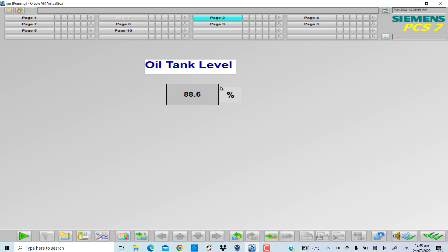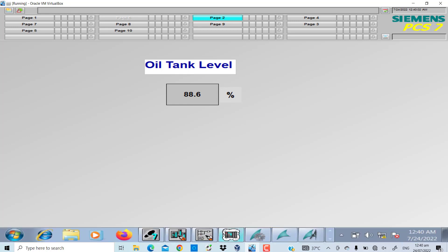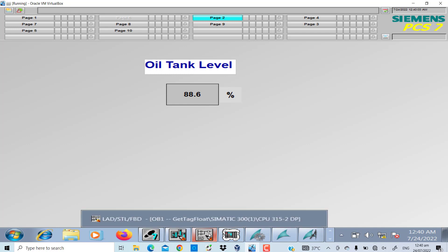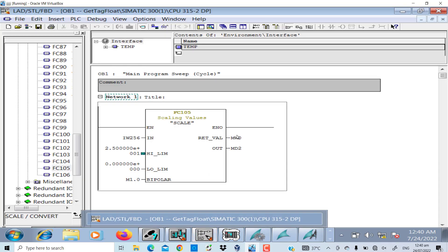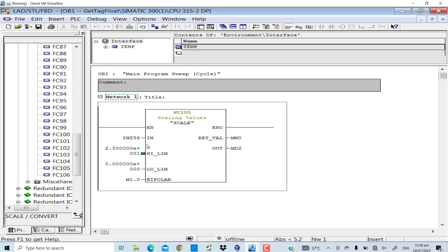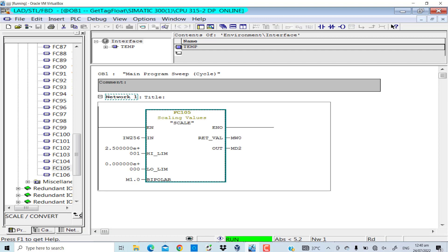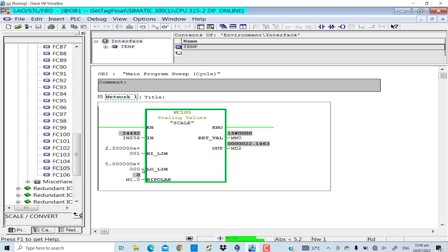If I go to the logic and monitor the program, the scale of the oil tank level is from 0 to 25. The hex value coming from the field through the analog input card has been scaled between 0 and 25, and the result is stored in the double word MD2.